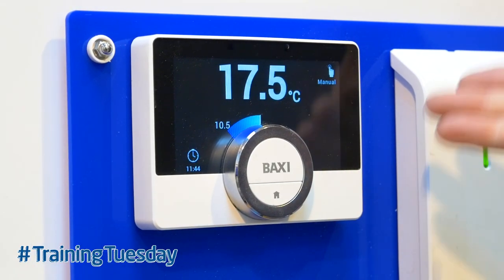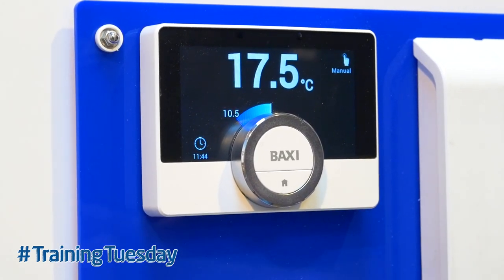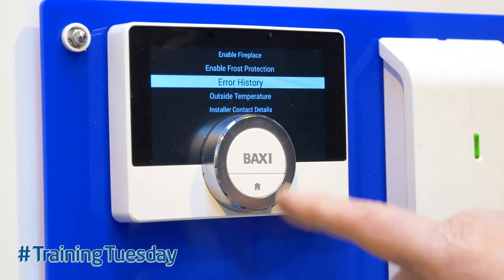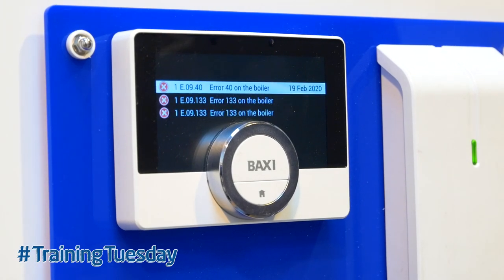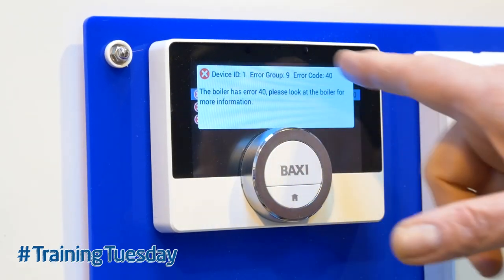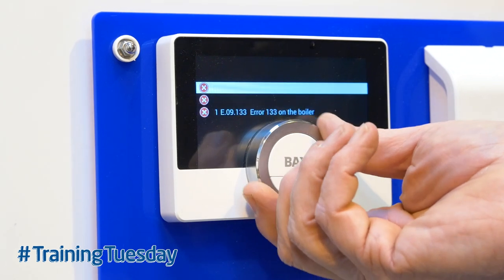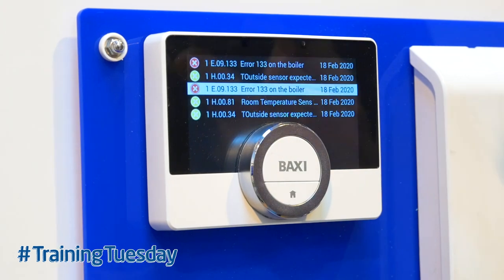The error has disappeared because E40 is a blocking code, so it's not there all the time. From an installer's point of view, they may not see that error, but we can access the error code history just by pushing the Baxi button and scrolling around to error histories. Push the button again — it takes a few seconds for communication with the uSense. There we've got error 40 on the boiler; we expand it and it gives us that error code. As we scroll down we can see other error histories — some aren't dated because the date wasn't put in — and there are a lot of different errors on there, though these aren't genuine errors; they're errors I've put on for demonstration.